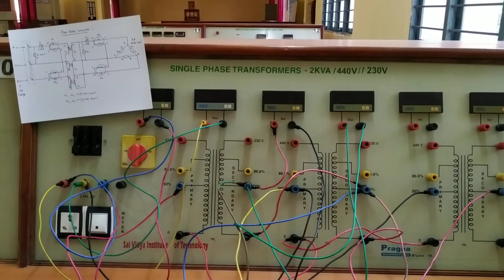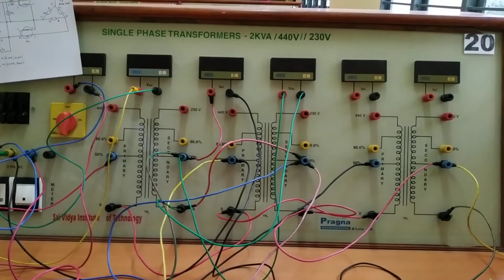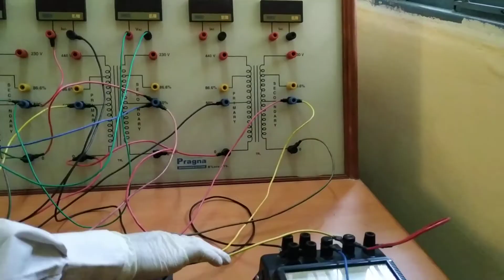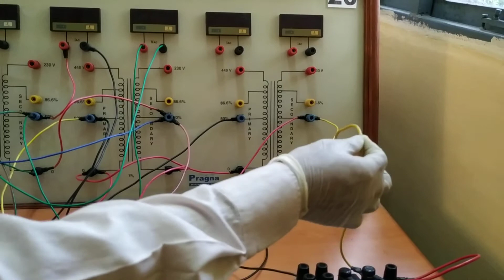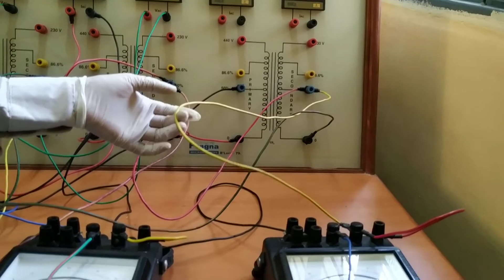Further, from S1 of the second transformer, it goes to the Y terminal of the three-phase delta connected load, that is the resistive load bank. Then from S1 of the third transformer, it goes to wattmeter W4's M terminal, and from the L terminal it goes back to the resistive load bank.